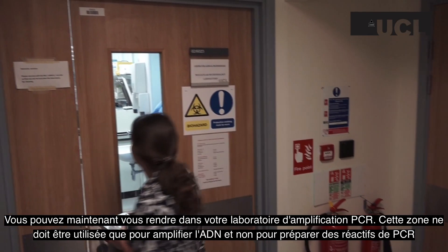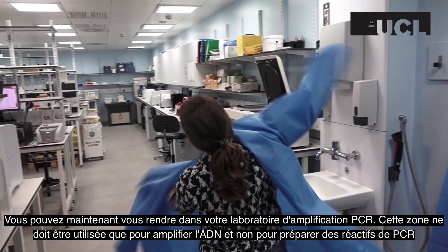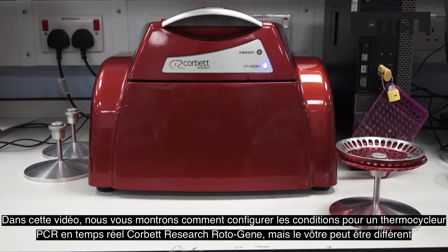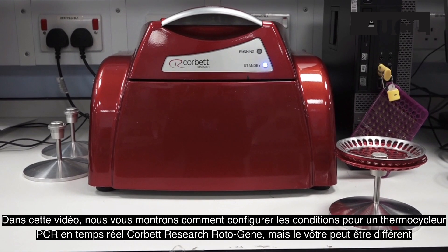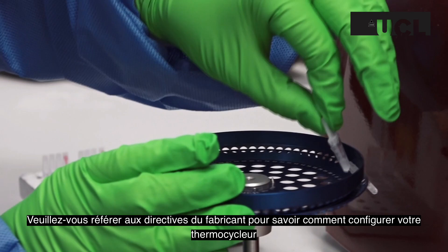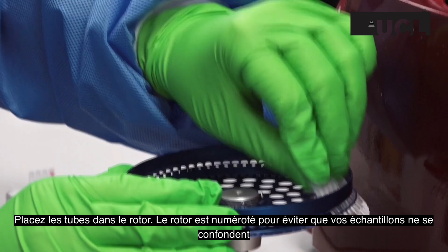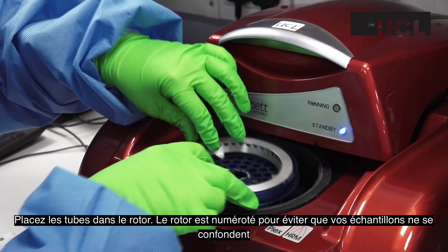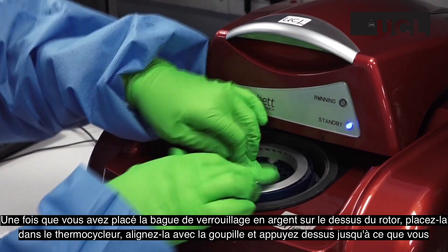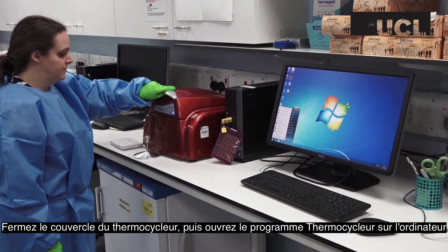You can now proceed to your PCR amplification laboratory. This area should only be used for amplifying DNA and not preparing PCR reagents. In this video, we are showing you how to set up the conditions for a Corbett Research real-time PCR thermocycler Rotor-Gene, but yours may be different. Please refer to the manufacturer's guidelines for how to set up your thermocycler. Place the tubes into the rotor. The rotor is numbered to ensure that your samples do not get confused. Once you have placed the silver locking ring on top of the rotor, place it into the thermocycler, lining it up with the pin and press it down until you hear it click.